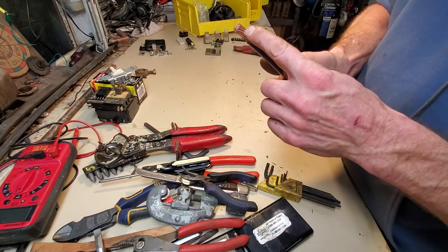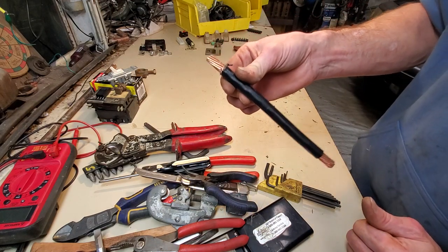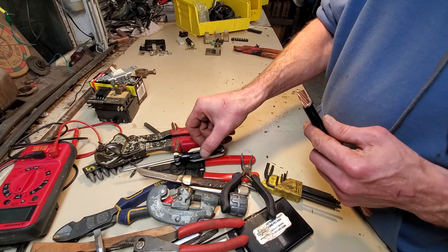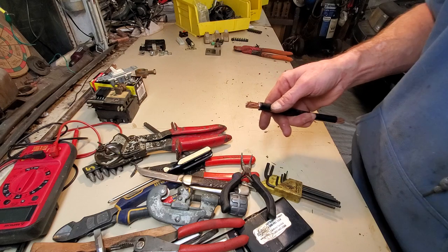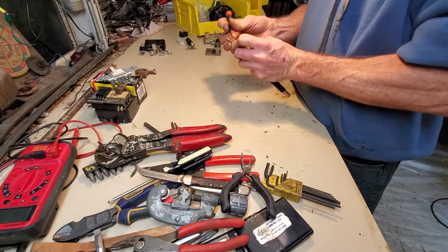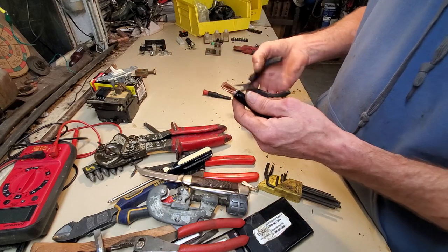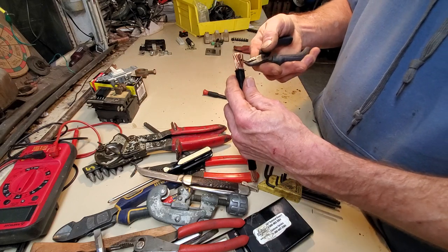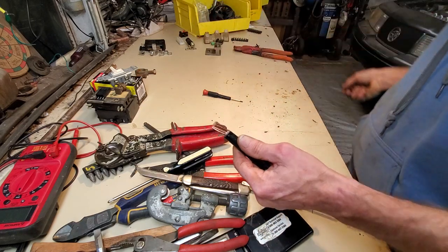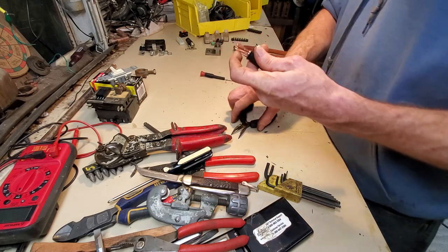So now they go to use this end as a load-bearing piece of your electrical infrastructure. Let's do a little forensics here. I'll get a single conductor out. As a result of using the lobster claws — watch this. One, two — it broke. Interesting. I wonder why it broke.